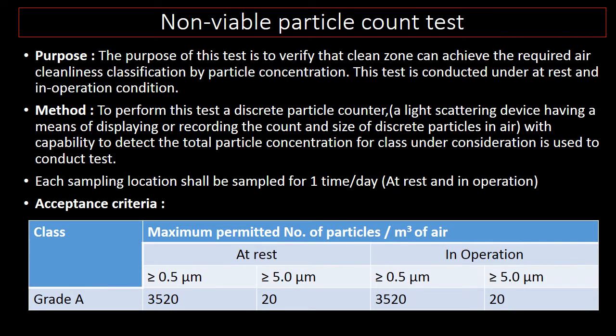The next important qualification test is the non-viable particle count test. The purpose of this test is to verify that the clean zone can achieve the required air cleanliness classification by particle concentration. This test is conducted under at-rest and in-operation conditions. To perform this test, discrete particle counters — light scattering devices having a means of displaying or recording the count and size of discrete particles in air — are used. Each sampling location shall be sampled one time per day under both at-rest and in-operation conditions.